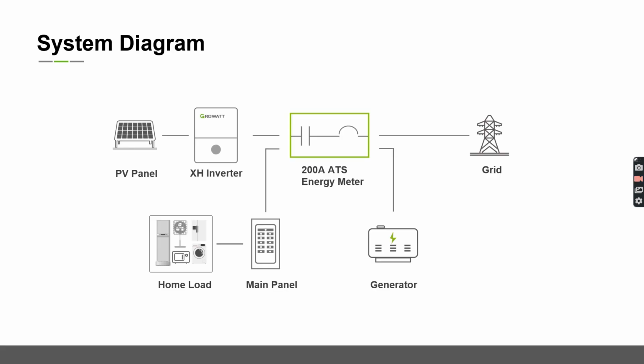Here, you can view how our ATS will be fitted into the PV system for backup power. The ATS will be connected to the inverter, grid, and main panel to allow for backup power to your home loads. A generator can be added for an additional source of backup power. In primary operations, the ATS will draw power from the utility or inverter output to power the home loads, but in a backup situation, the ATS will switch over to the inverter's backup port to provide seamless power for home consumption.